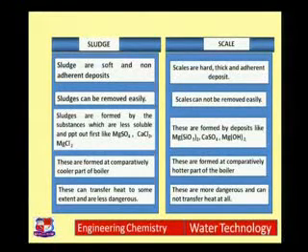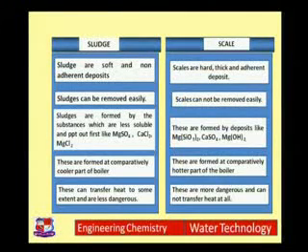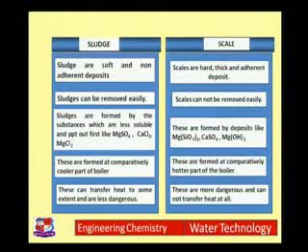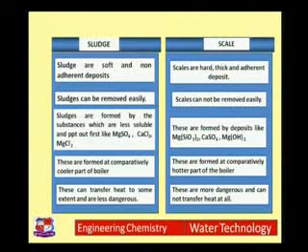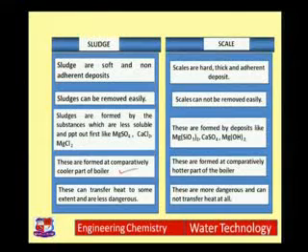Sludges are formed by substances that are less soluble and precipitate out, like magnesium sulphate, calcium chloride, and magnesium chloride. Scales are formed due to specific chemical reactions in the boiler, such as magnesium silicate formed due to presence of silica, calcium sulphate whose solubility lowers down, and magnesium hydroxide formed due to hydrolysis of magnesium chloride. Sludges form at comparatively colder regions of the boiler like inlet or outlet pipes.